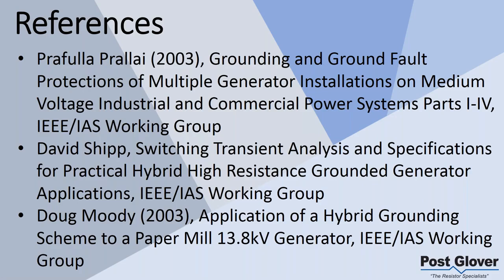One of your very early slides, John wanted to know what is meant by faulted circuit must be segregated. Basically, all it means is if you have a low resistance ground system, or even a hybrid ground system, you're going to be tripping. It just means that you're going to have to open a breaker, and a lot of times it's going to be your whole system, so it's just going to be shut down. But sometimes it's going to be segregation. Tripping is all I'm saying.